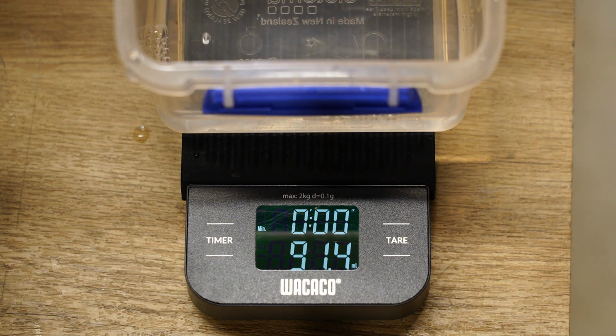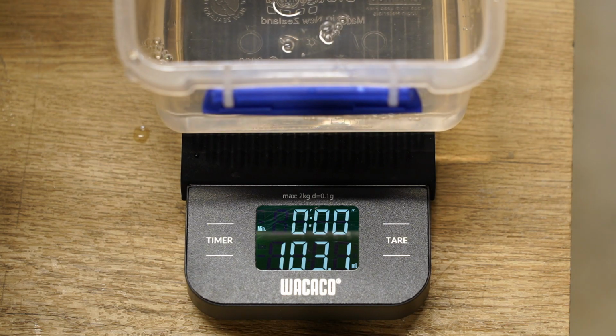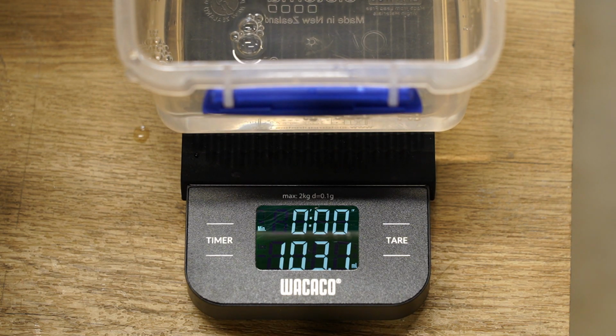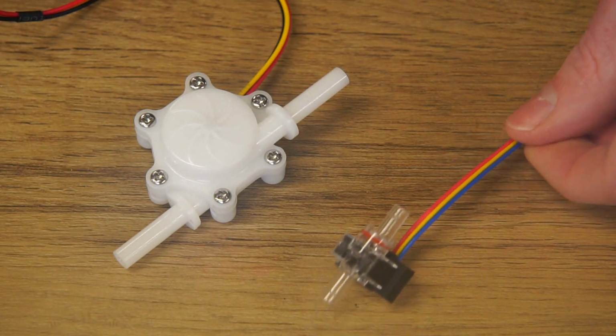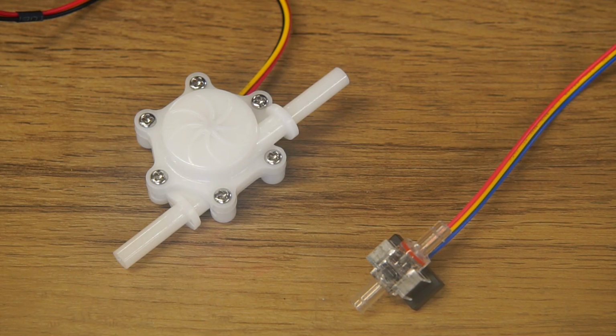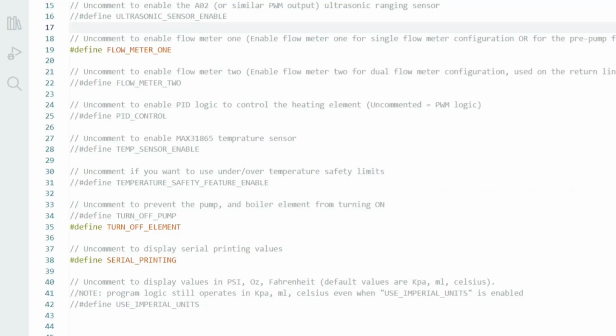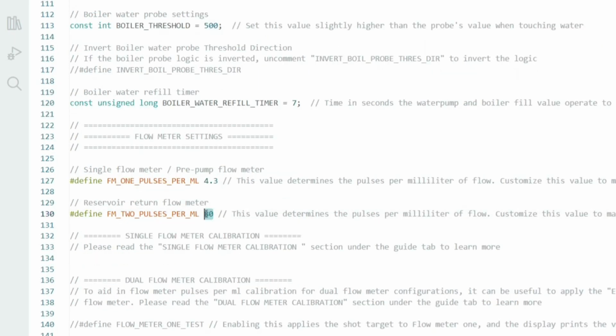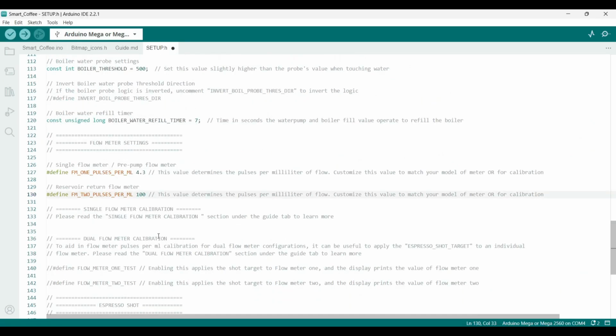For single flow meter configurations, calibration would be complete at this point. For dual flow meter configurations, I can move on to calibrating the second flow meter that's on the return line. I enabled the second flow meter on my setup tab and entered 100 pulses per mil as a starting value.